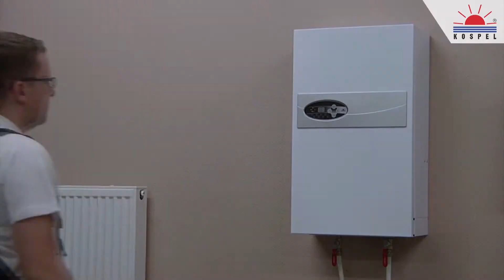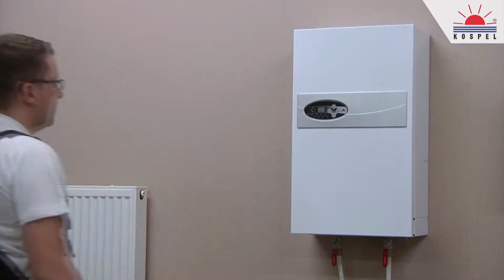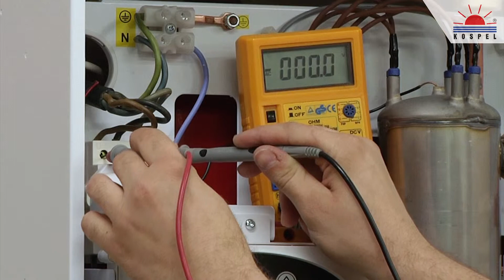The control panel may display some of the boiler faults using its indicators. If the indicators on the control panel are unlit, check the main power input of the boiler. If the main power input voltages are correct, the power supply systems can be damaged, or the WT3 thermal cutout was activated. Please contact an authorized Kospel service.